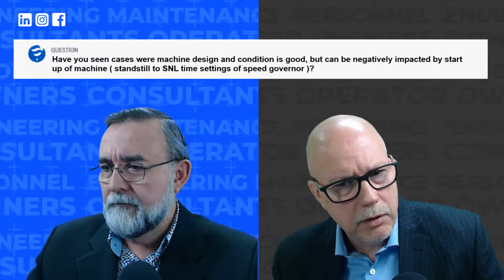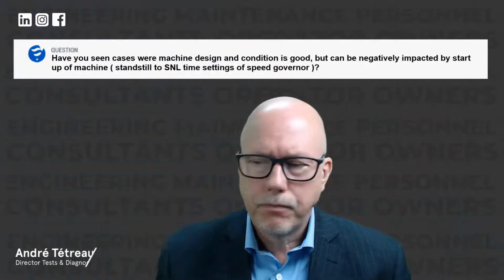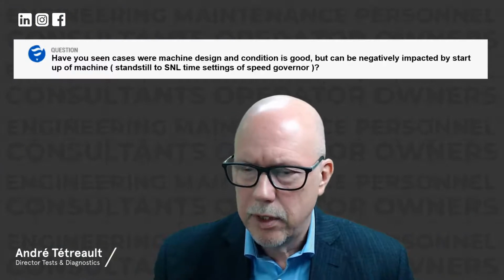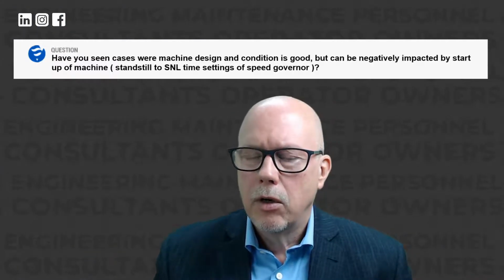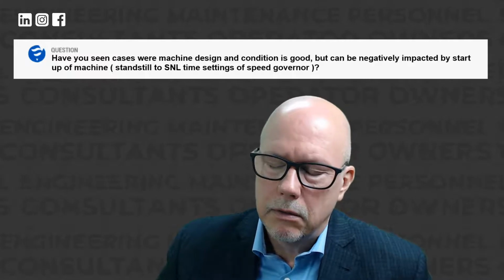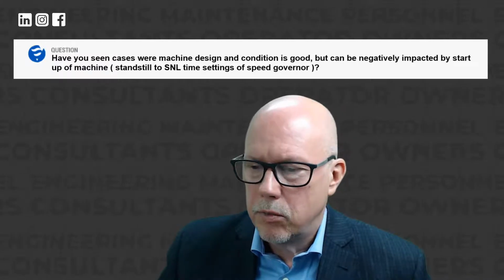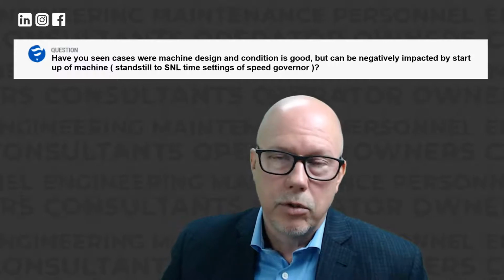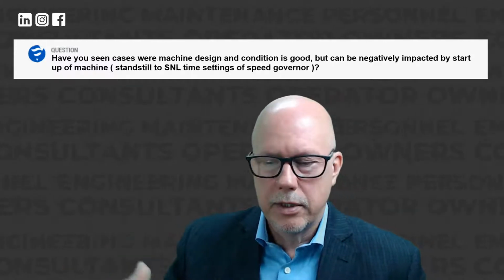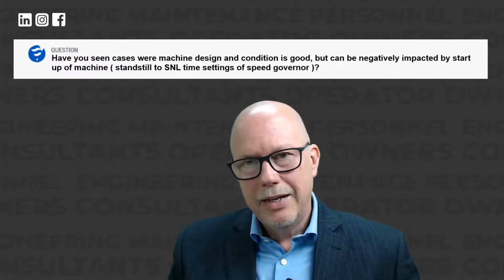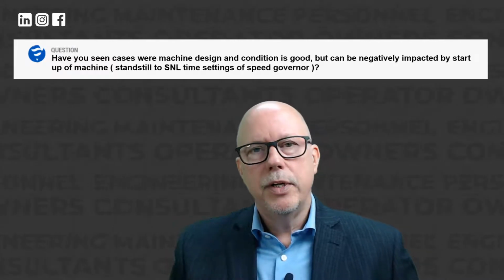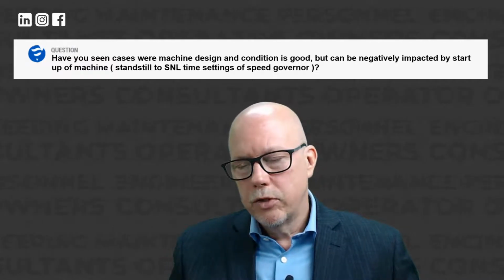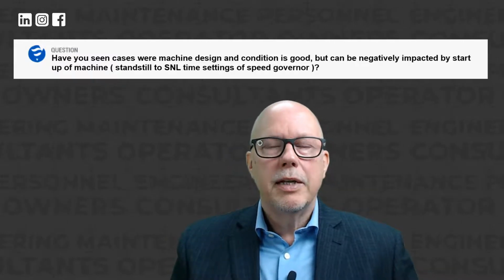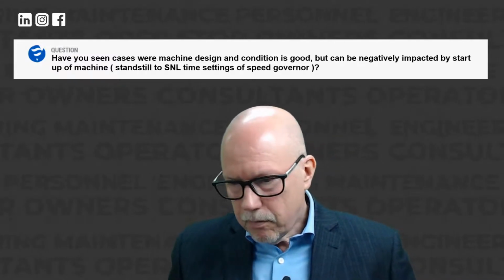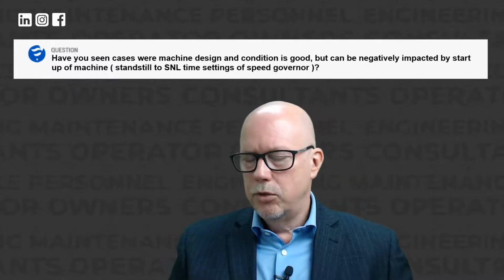Yes. The first one that comes to mind is a power station in Brazil where the OEM had offered four units with a new rotor design—new at the time. The design was that the rotor rim would be a tight shrink fit, but if the unit reached 110% speed during an overspeed or load rejection, the rim would be allowed to float to absorb the energy. So the design was simple, but at that time it was a new concept.